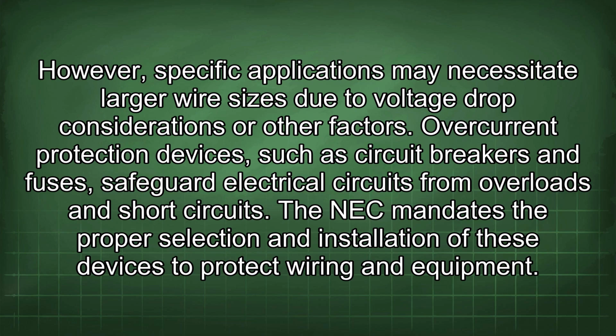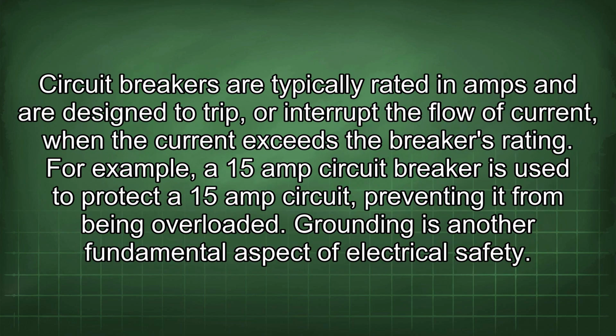Overcurrent protection devices, such as circuit breakers and fuses, safeguard electrical circuits from overloads and short circuits. The NEC mandates the proper selection and installation of these devices to protect wiring and equipment. Circuit breakers are typically rated in amps and are designed to trip or interrupt the flow of current when the current exceeds the breaker's rating. For example, a 15-amp circuit breaker is used to protect a 15-amp circuit, preventing it from being overloaded.